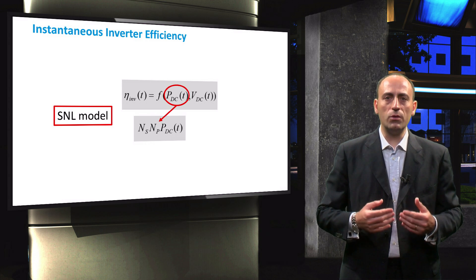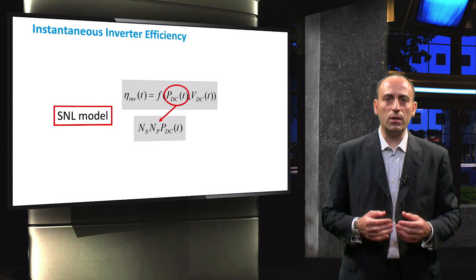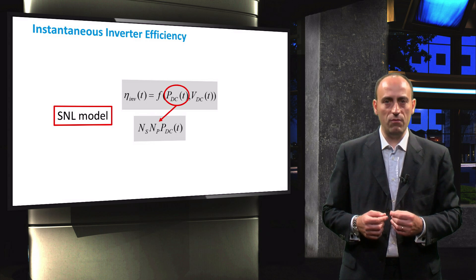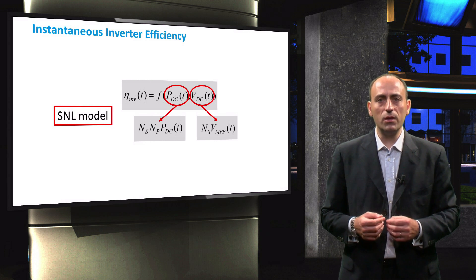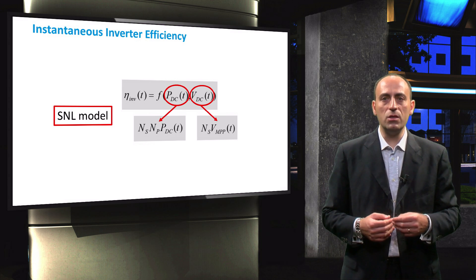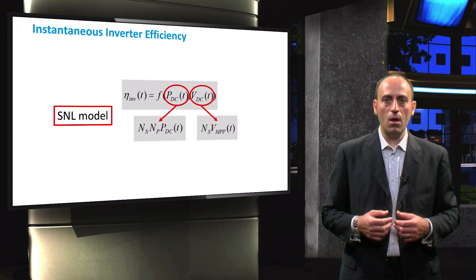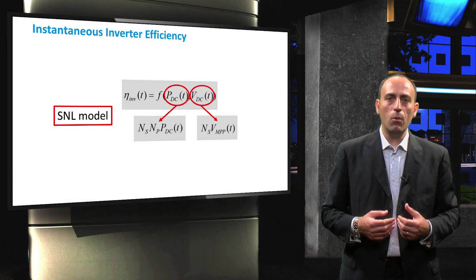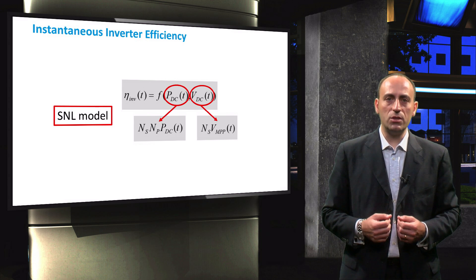The DC power is the product of total number of modules and the power generated by one PV module. The DC voltage is the product of maximum power point voltage of a PV module and the number of series connected PV modules. Through the SNL model, we obtain the instantaneous efficiency of the inverter.